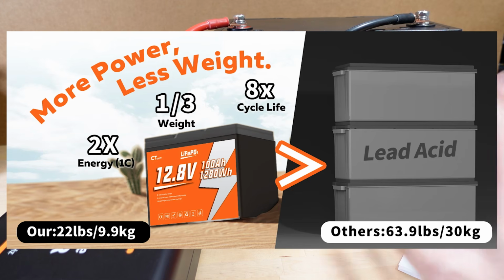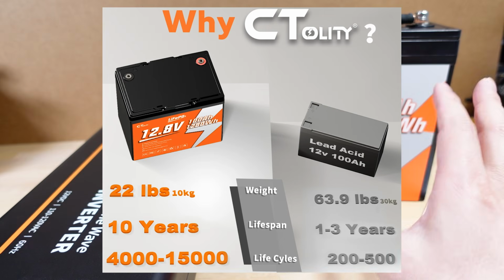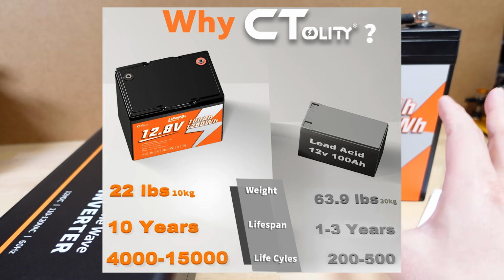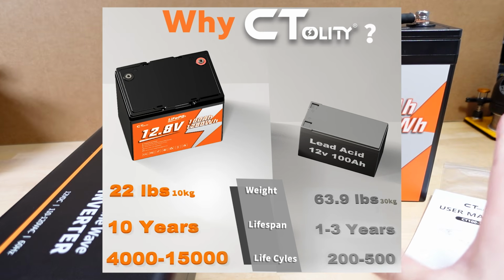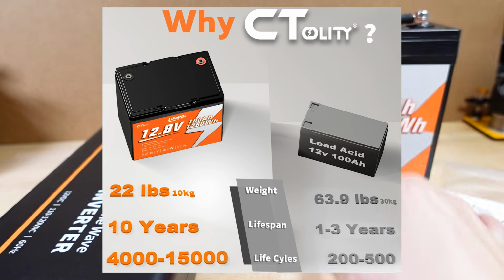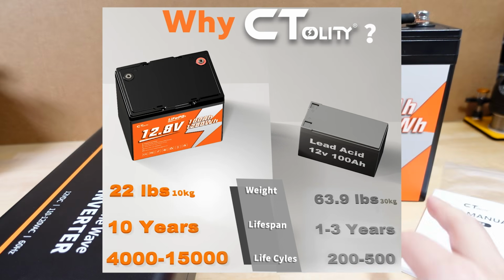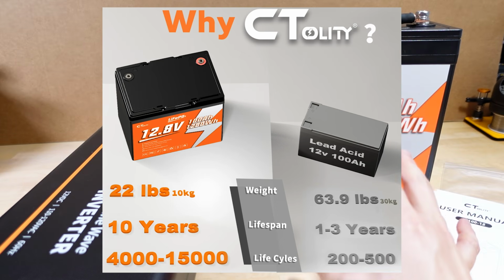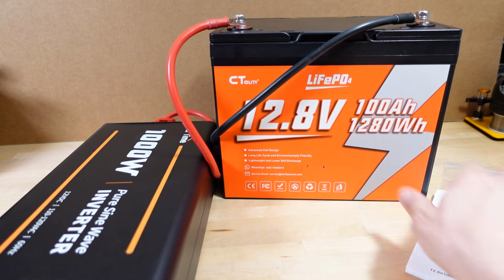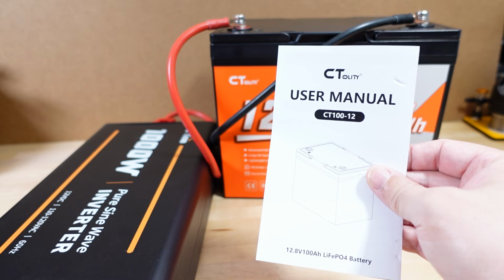The battery weighs about 23 pounds, or around 10.5 kilograms. So compared to a typical 12 volt lead acid battery, it's going to weigh about a third of the weight, and it's going to have about double the capacity. Also, the lifespan is going to be significantly more. Lead acid usually lasts about 1 to 3 years before it dies. Lithium iron phosphate will typically go about 10 years, which means you're going to get like 4,000 to 15,000 cycles.